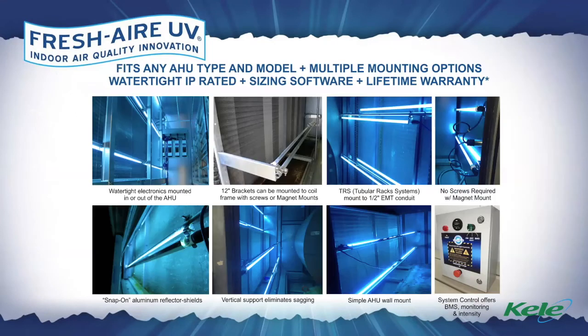Now we do have optional accessories, everything from reflectors. So case in point, the bottom left picture, you see a reflector there. These are clip-on reflectors. In some instances, they want to install UV systems on a very fouled and dirty coil, and they want to take all that UV energy and direct it where they want it, which is the coil itself. So they'll use the clip for a few months, and then after the coil is eventually clean, they would remove the clip so you could irradiate 360 degrees, address the walls and the blower housing and other areas of the air handling unit, as well as treat the air as it's entering and obviously exiting.